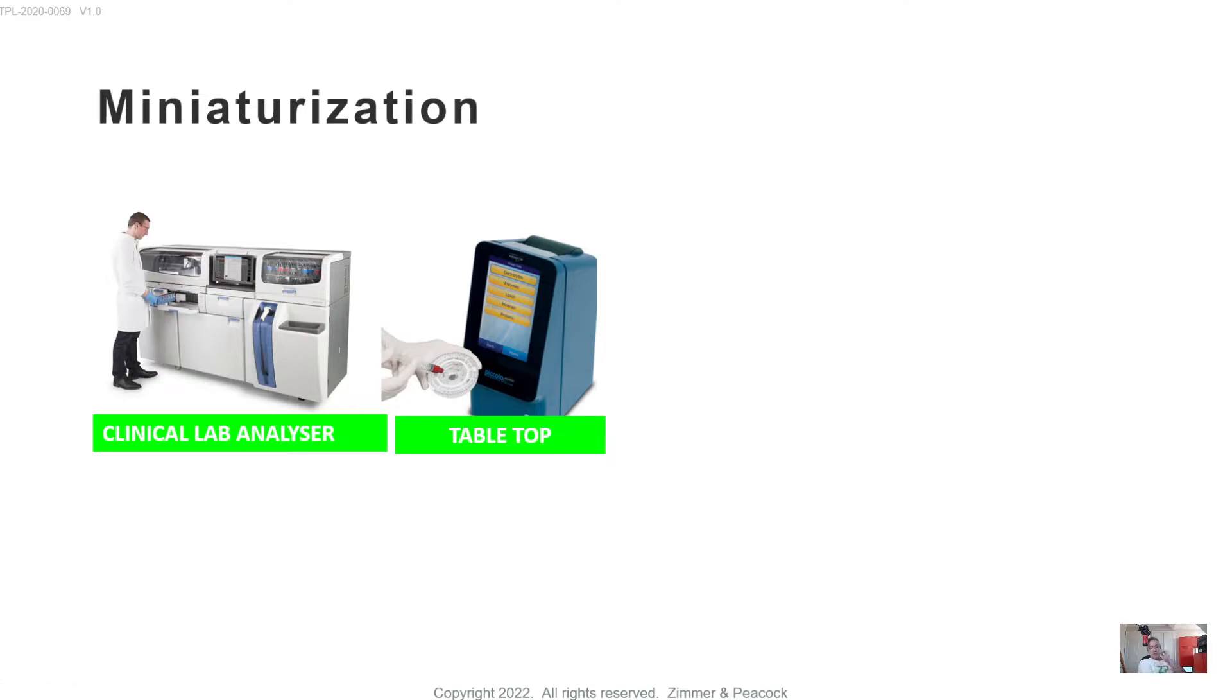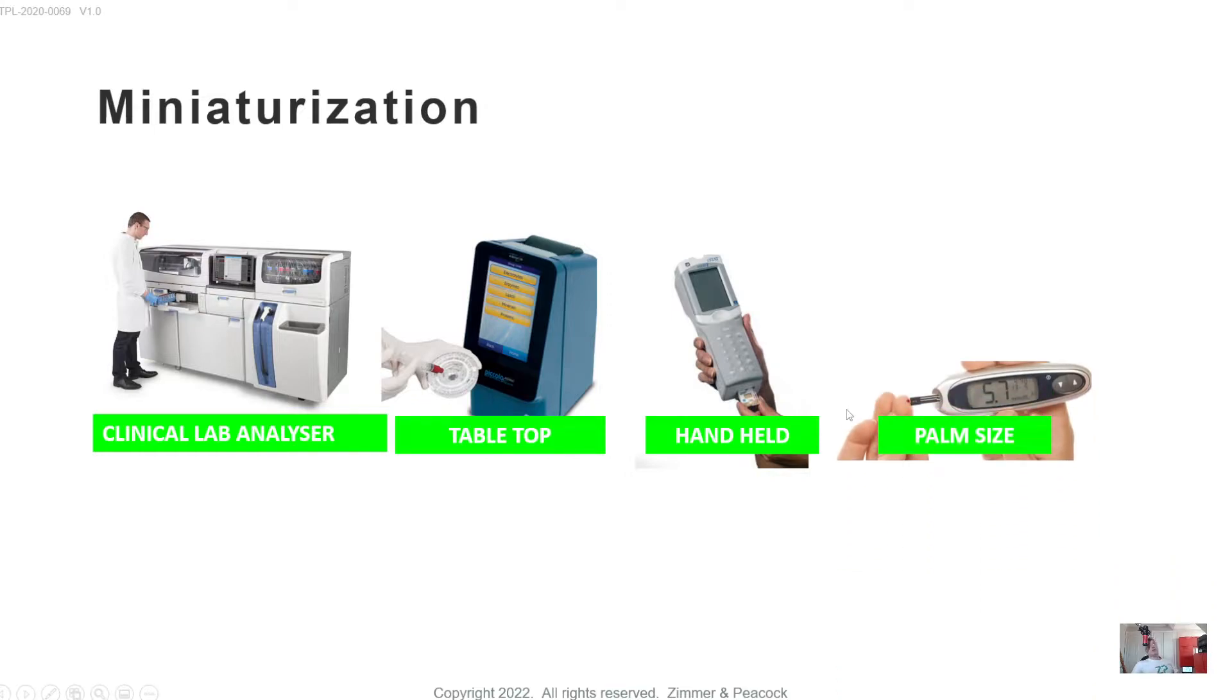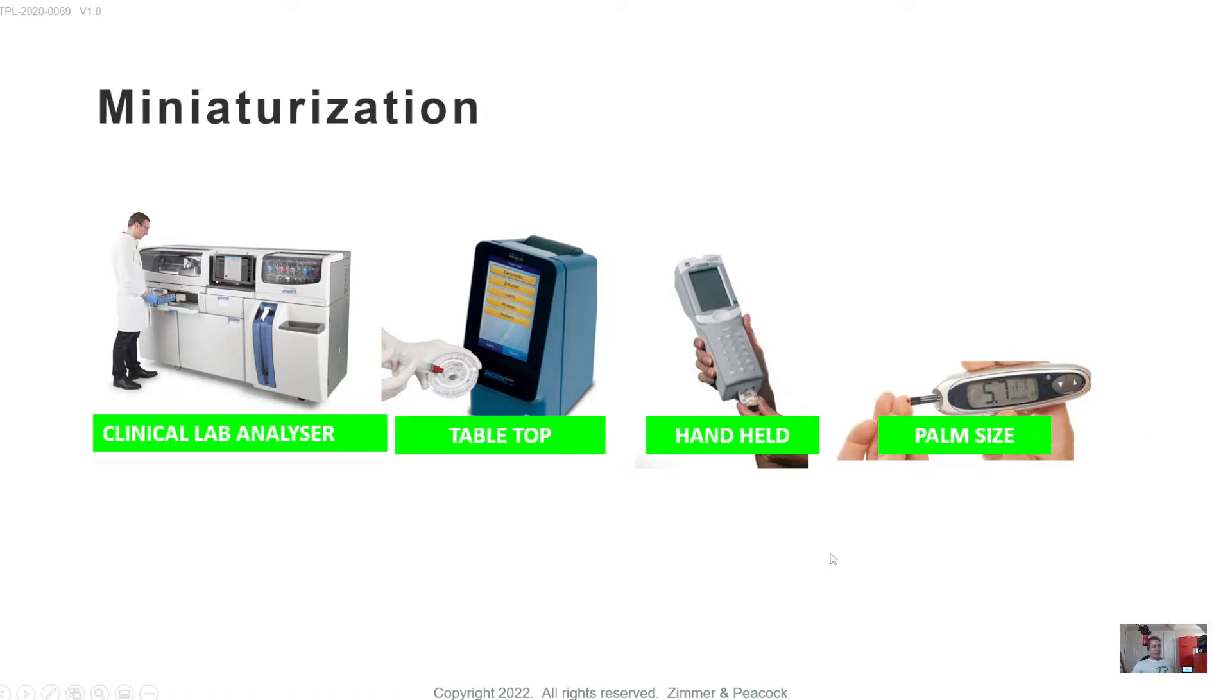This particular tabletop device allows one sample at a time, but it can do a comprehensive metabolic panel within its own little cartridge. There's been a shift towards handheld devices. This is one of the grandfather handheld devices, but it does essentially one analyte at a time. And then, very much driven by the glucose or diabetes testing space, there are these very small form factor meters with little disposable strips. So there's definitely been a movement from hospital-only centralized blood testing down to almost consumer electronics type at-home testing.